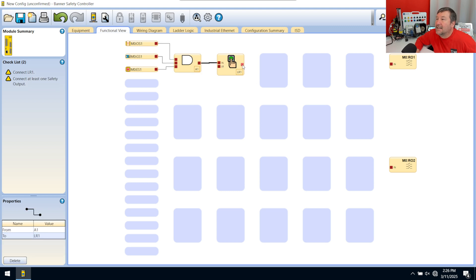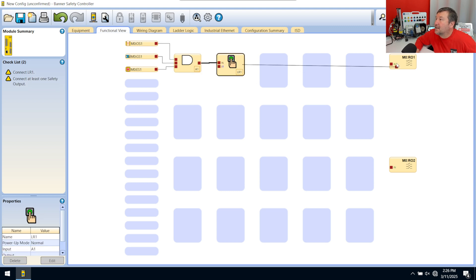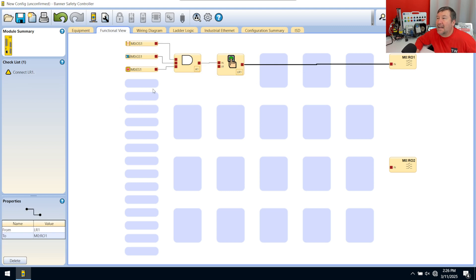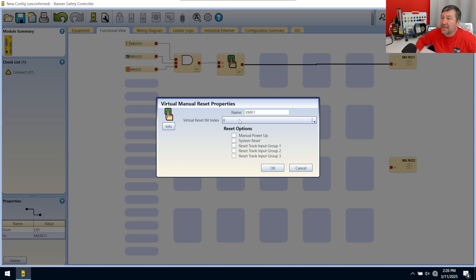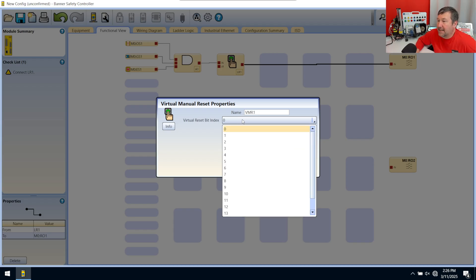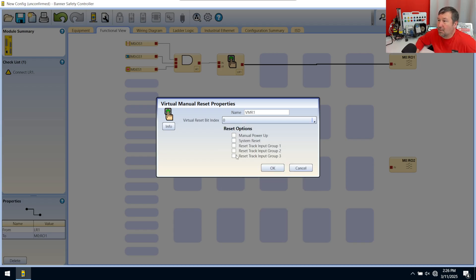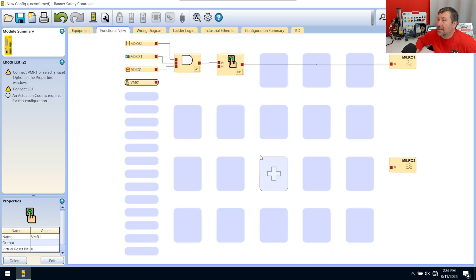And then this goes out over to here. And then we need our reset input. And we're going to go grab a virtual non-safety input because we are going to do this over Ethernet. And that'll be a virtual manual reset. And our reset bit address, we are going to use zero on. And click OK.